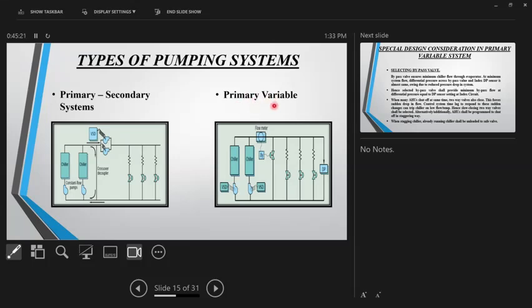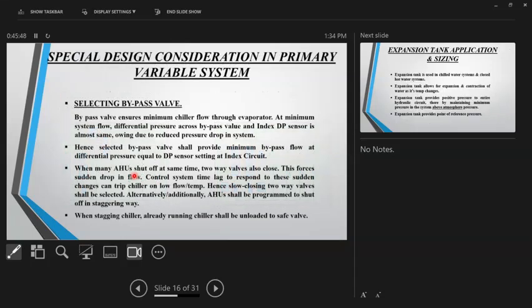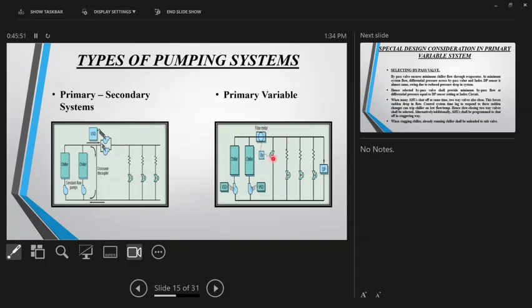In primary variable, obviously you don't have two sets of pumps. It's only one speed of one set of pumps that is responsible to pass the water from the chiller to the last load. So this we all know. The speed variation of the pump in this as well as in this follows the same theory which I showed you in earlier slides, the pump speed modulation technique. Now, sorry, let me go back. You saw a primary variable valve here, which is also known as the minimum flow bypass valve.